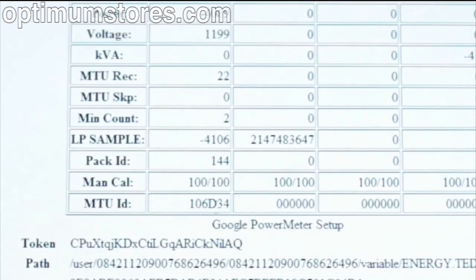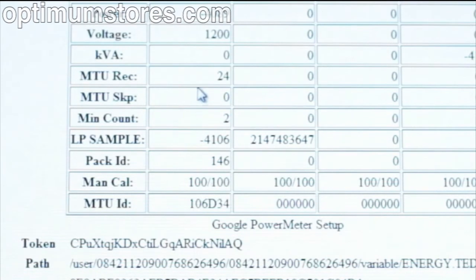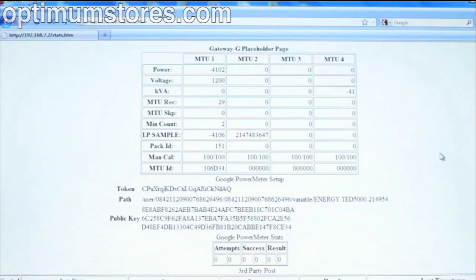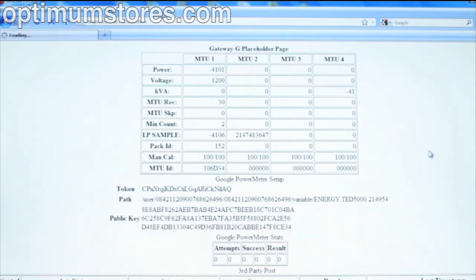Note the MTUREC line and MTUSKP line. This is the ratio of packets of data received from the MTU versus those missed. This ratio should be about 80 to 20 or better. If the ratio is poor or the MTUREC is zero, you likely have a power line communication, or PLC, issue, and we will address this in the next video.